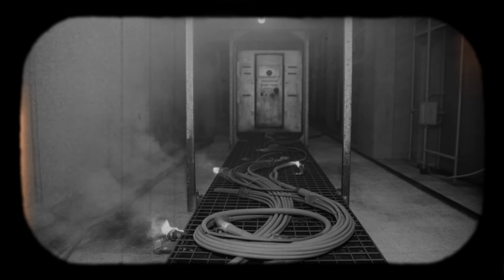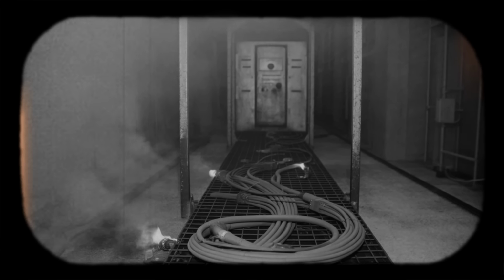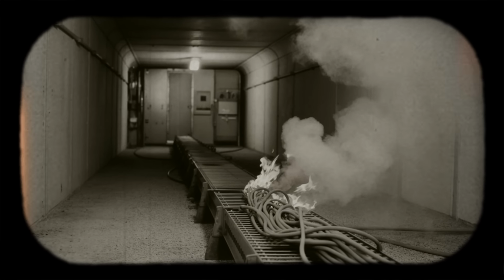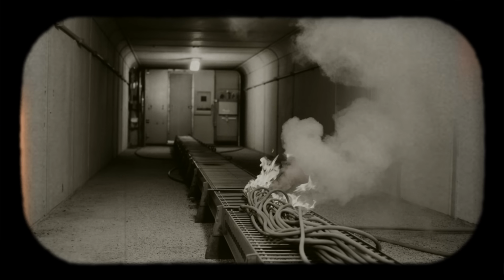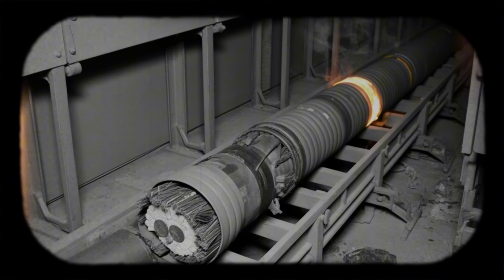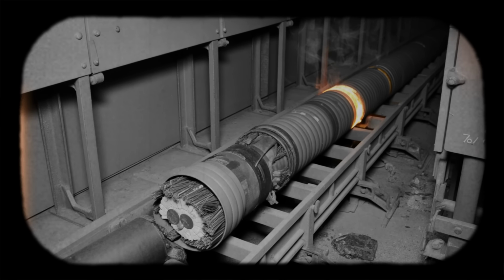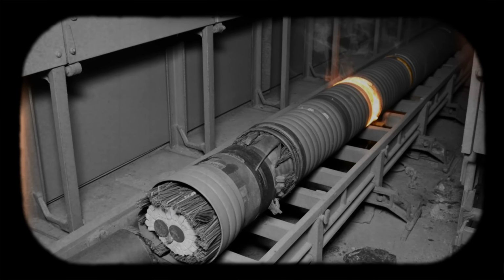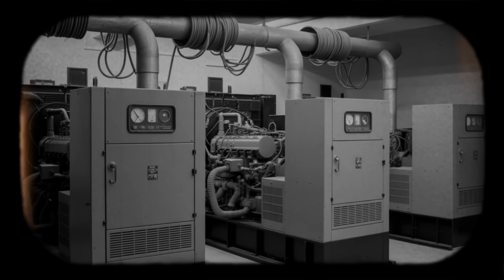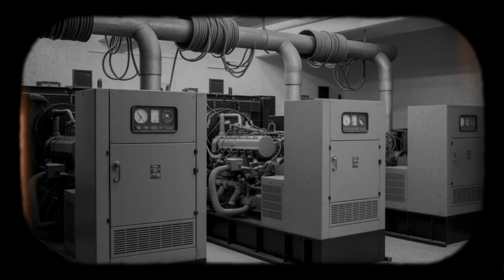But it worked. For several hours, this improvised cooling arrangement kept the core safe. The US Nuclear Regulatory Commission and NEA reviews would later highlight Greifswald as a teaching case, how equipment used outside its design basis can provide accident management capability, and how operator ingenuity can bridge gaps when design systems fail. The extraordinary method bought time to assess damage, time to search for alternative power sources, time to plan the next steps towards stable shutdown cooling. The immediate crisis, loss of all designed cooling paths, was contained, but the plant remained far from a controlled state.